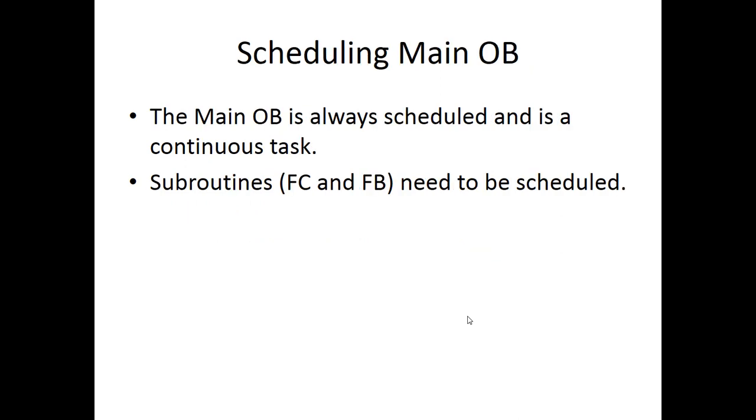Scheduling on the main OB, it's always scheduled, and it's a continuous task. And then we ran our subroutines, FC and FB, out of the main, and we could conditionally or unconditionally schedule the FCs and FBs.